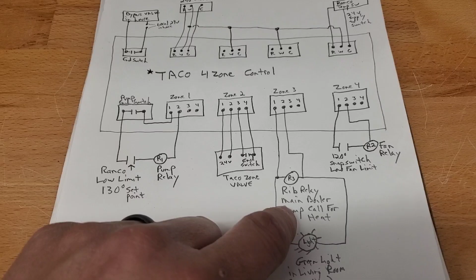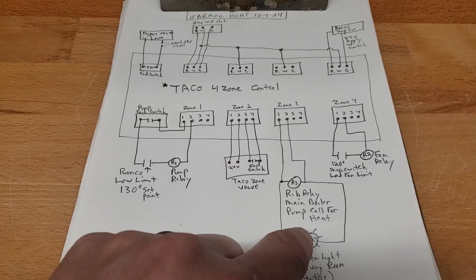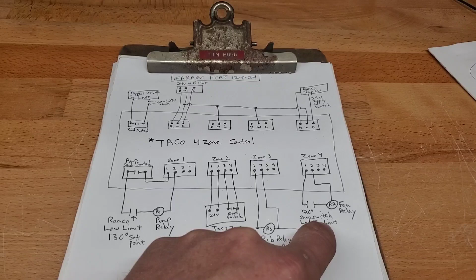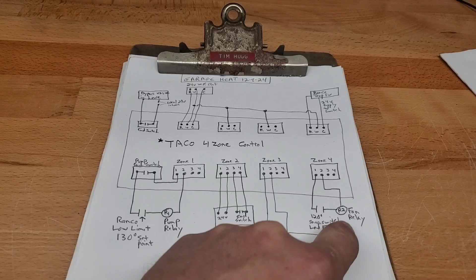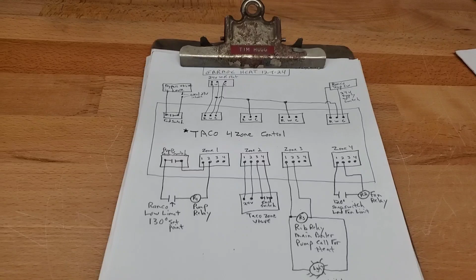That also turns on a relay in the house and a green light in the living room that lets me know that the garage is calling for heat. So if I'm over there and I see the green light on, I know I forgot to turn the heat off. But that will tell the main boiler pump to turn on, because that supplies this garage, and then this is just a booster pump. And then I put a snap switch on the hot water coil, because this is 24 volts. I had to isolate that. When that reaches 120 degrees, it pulls in the fan relay, turns on my fan.